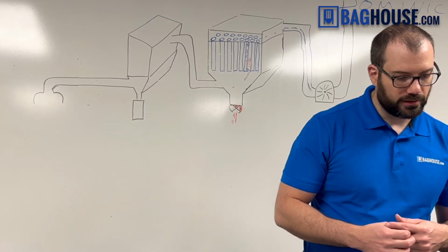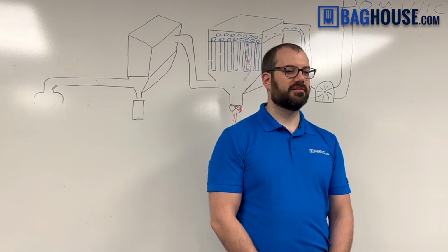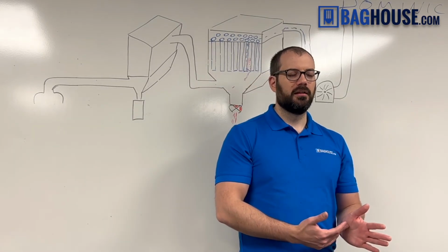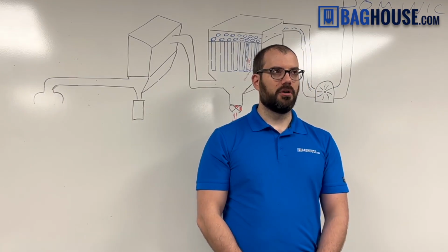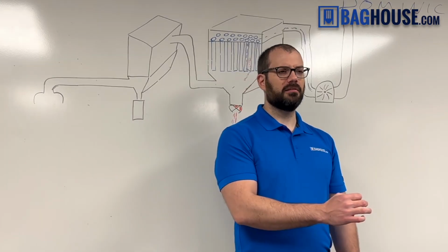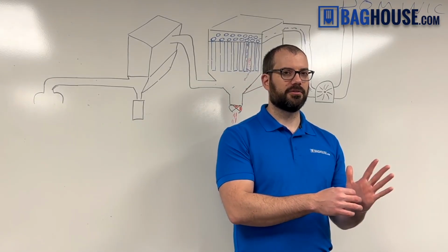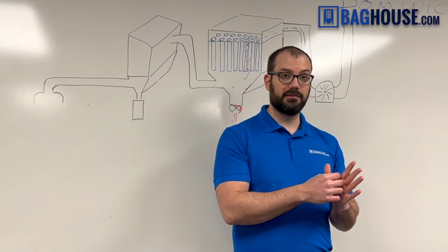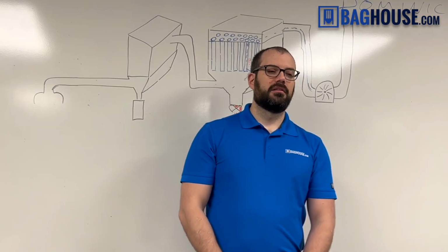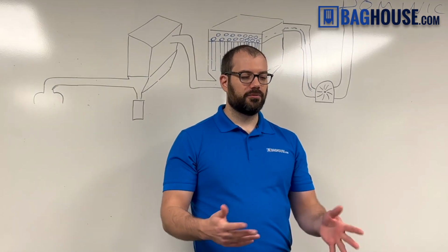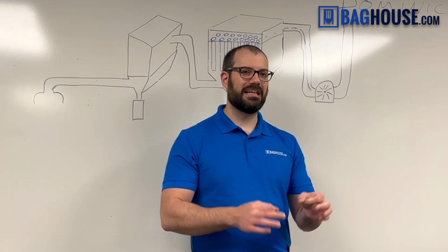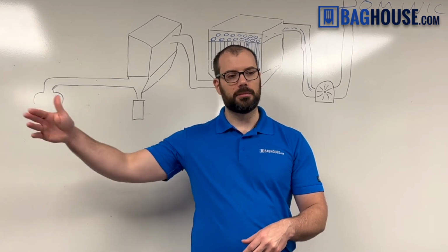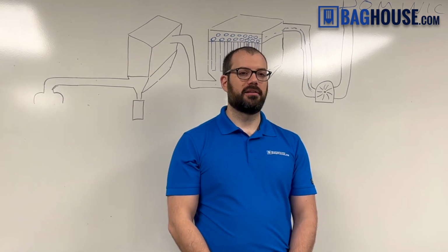What's number 4? So the collection efficiency is, for all the dust that comes in, what percentage of the dust is removed by the filter? So if 100 particles come in, how many particles does the filter stop? 98, 99, 100? So for the dust collector to be considered as working well, it needs to collect 99.9% of all the dust.